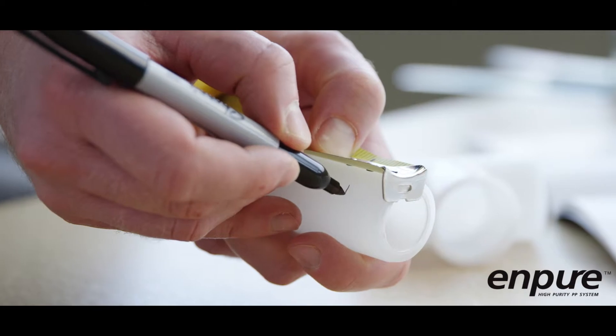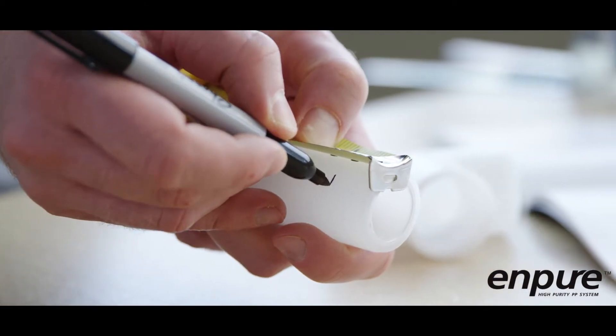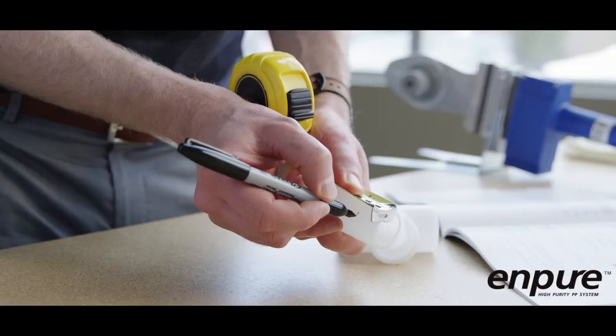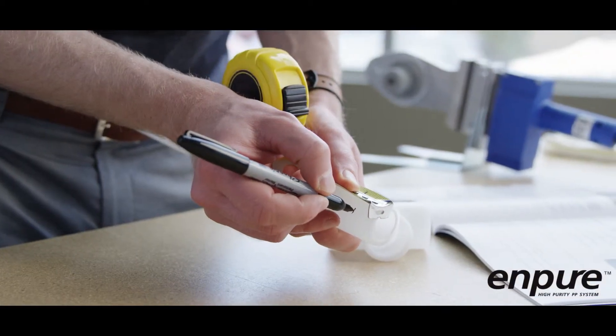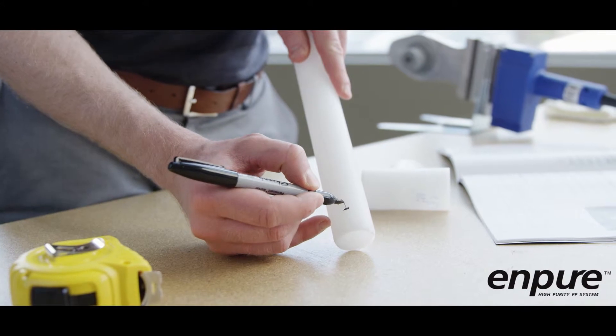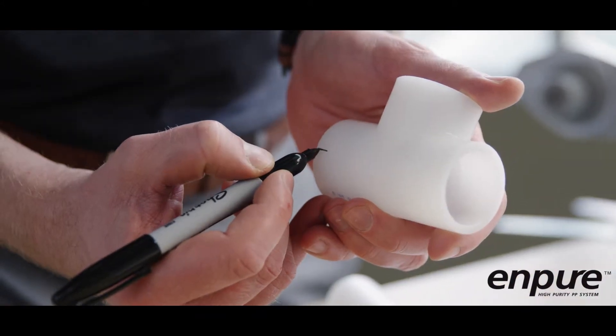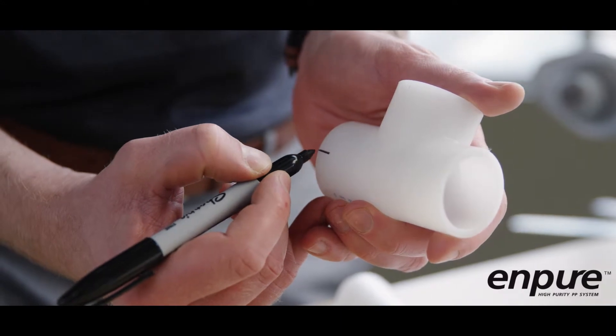The length of pipe to be inserted varies by pipe diameter. For the correct insertion length, refer to the table found in the enpure technical manual. Once selected, mark the pipe at the correct insertion length. Mark a longitudinal reference line on the outside of the pipe and fitting to prevent the two parts from rotating while the joint is being assembled.